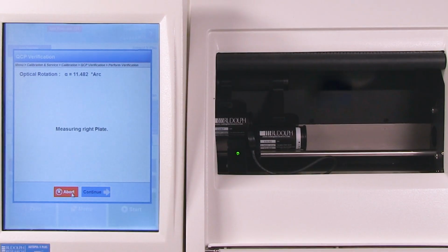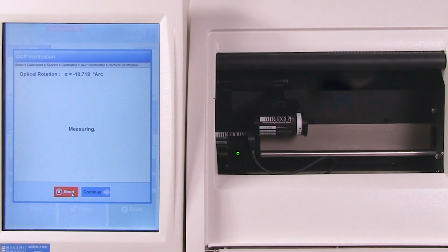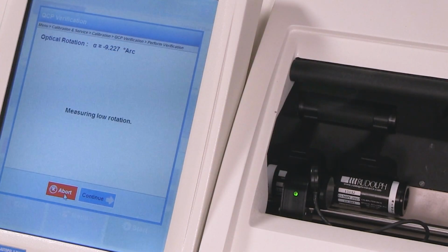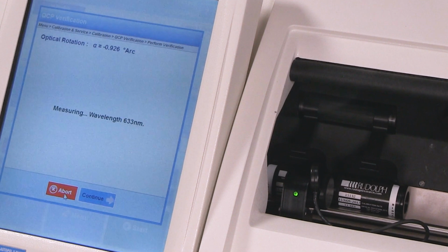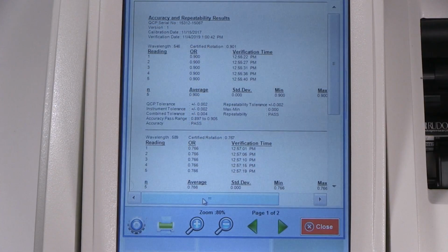Rudolph's calibration approach also includes a 3-point bracketing method. The instrument measures a high-rotation quartz plate, a low-rotation quartz plate, and then both plates together to establish a midpoint. This verifies linearity above, below, and near the target rotation, meeting the USP and EP requirements for bracketing calibration. Each measurement is logged automatically with user ID, time, and wavelength for full traceability.